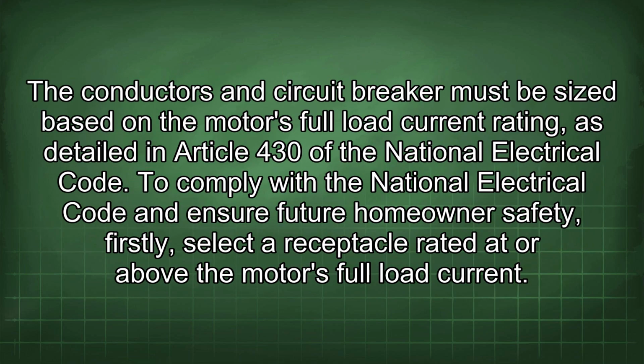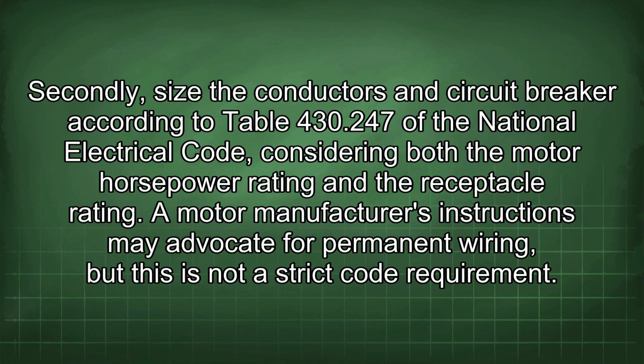The conductors and circuit breaker must be sized based on the motor's full load current rating, as detailed in Article 430 of the National Electrical Code. To comply with the National Electrical Code and ensure future homeowner safety, firstly, select a receptacle rated at or above the motor's full load current. Secondly, size the conductors and circuit breaker according to Table 430.247 of the National Electrical Code, considering both the motor horsepower rating and the receptacle rating.